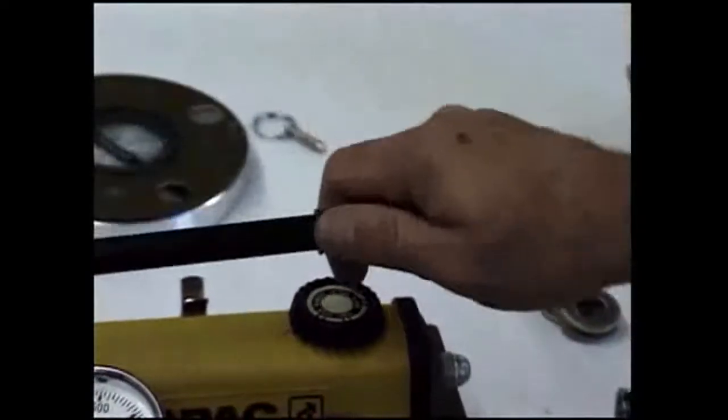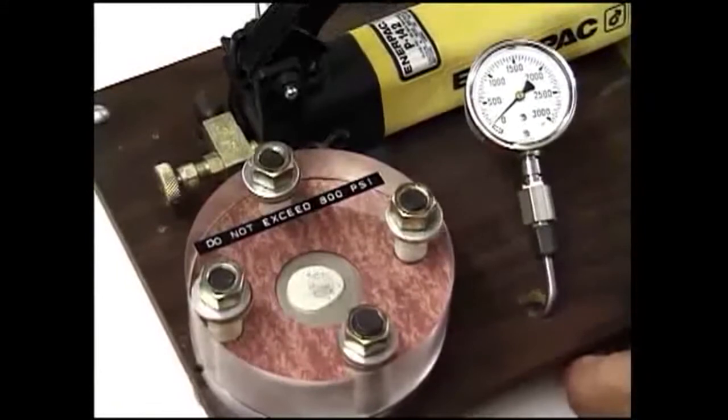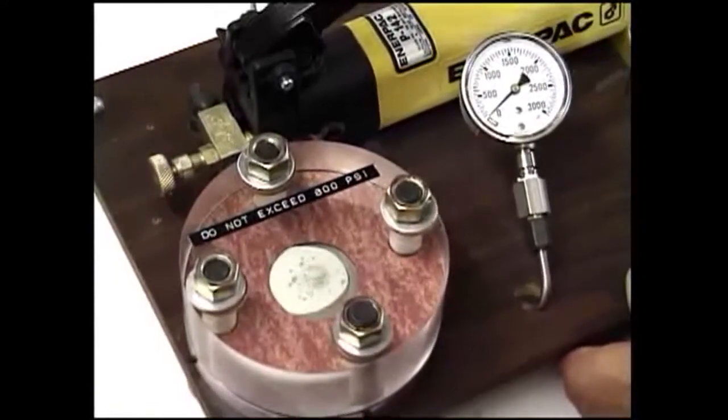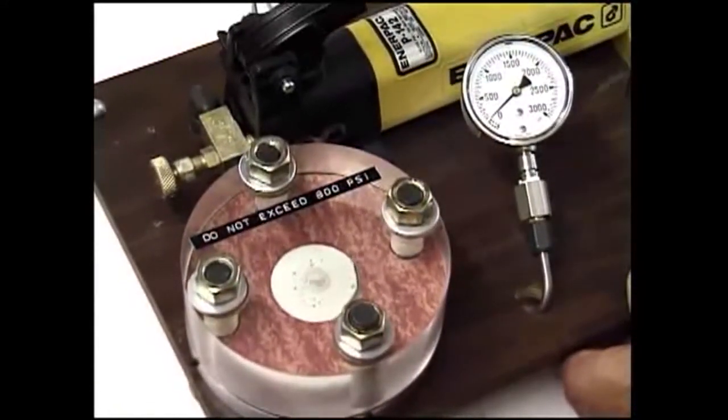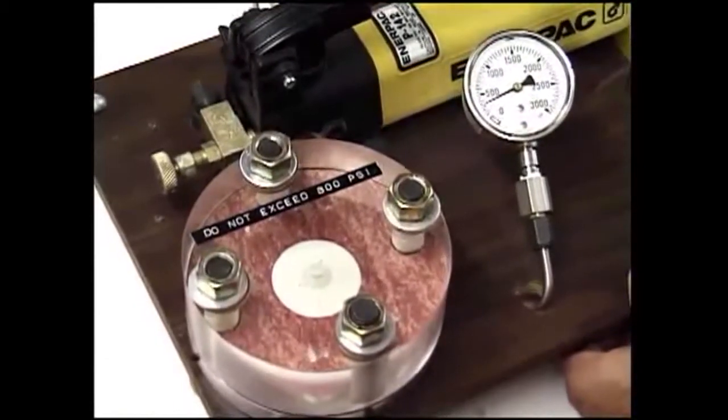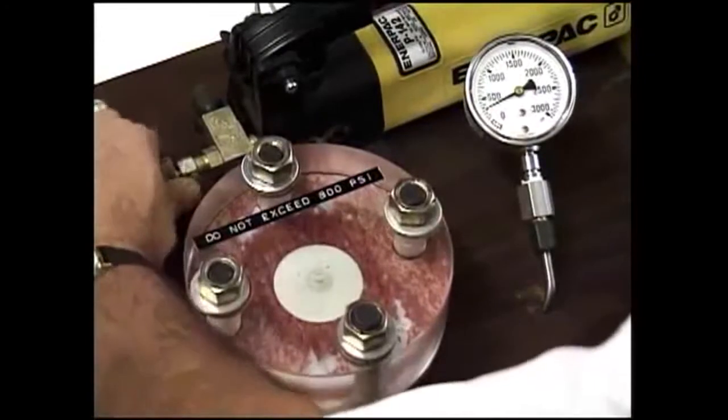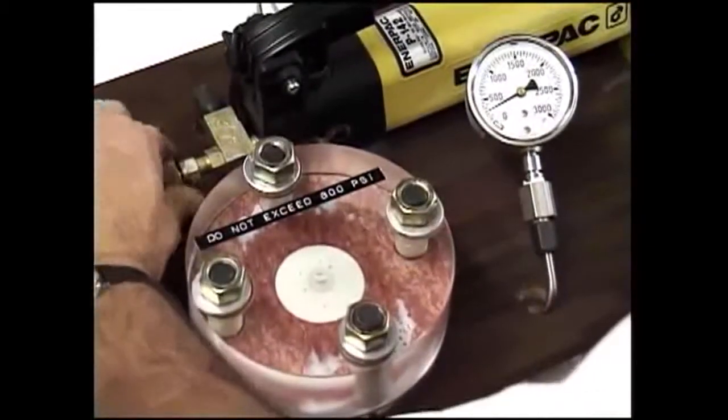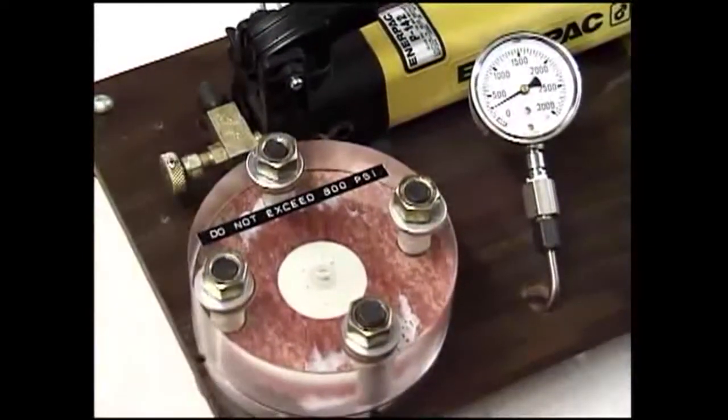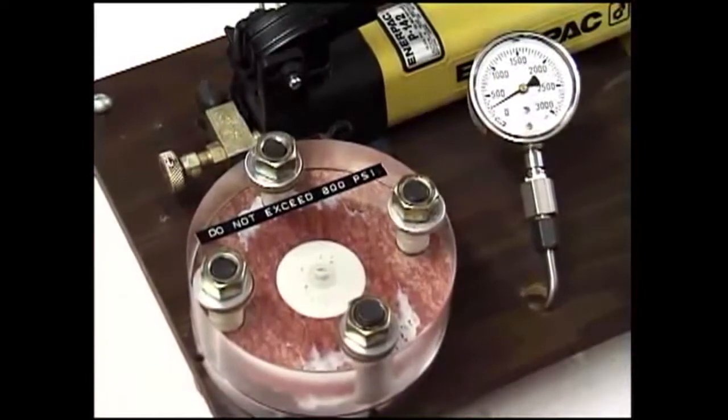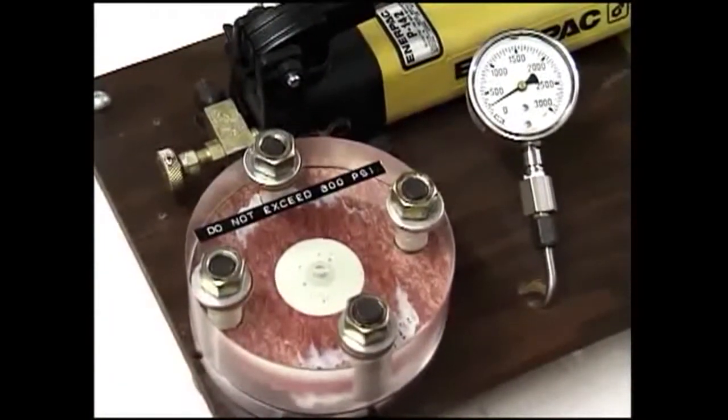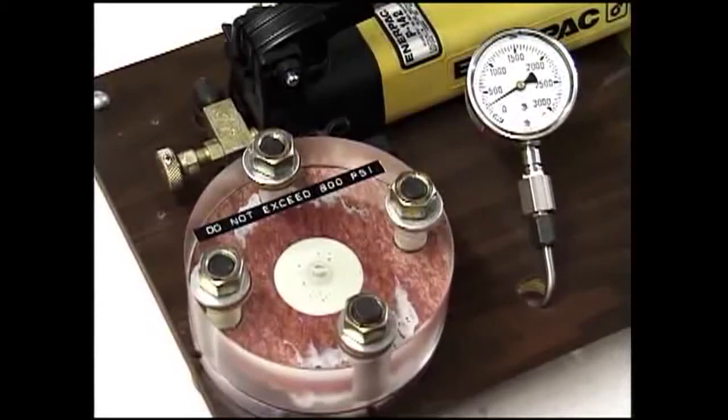A water-soluble cutting solution is pumped into the center of the gasket to simulate fluid flowing inside a pipe flange. Watch the gauge carefully. Notice how the pressure barely rises before numerous leak paths are detected, migrating across the gasket face. This gasket has failed miserably, and understandably so, seeing as we only applied 15 foot-pounds of torque to the nuts holding the gasket in the tester. A normal flat gasket would require massive amounts of torque, enough to actually crush the gasket in an attempt to hold 800 PSI.